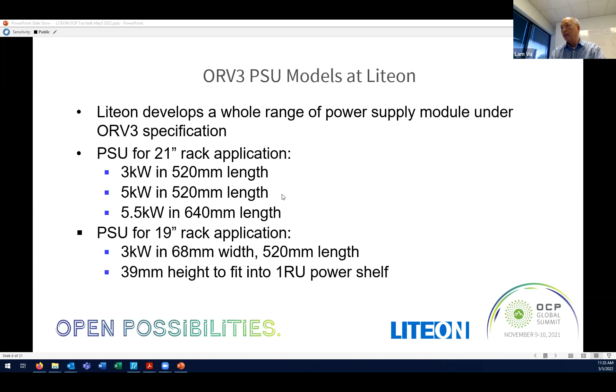For the power shelf itself, because the power supply conforms to ORV3, we can configure the power shelf differently. The power shelf has a 7-pin connector, so it will accommodate 208 delta, 240 delta, or 415 or 480Y.